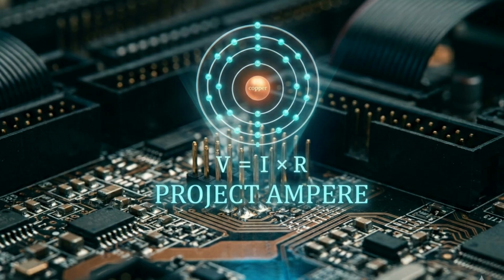When you reach up and flip that ground power switch on the panel, the automated bus logic says, a new power source has been manually commanded. I have checked it. The voltage and frequency are good. I will blindly accept it. And it does the switching automatically. It forcefully opens the APU contactor and instantly closes the ground power contactor. It prevents the human from accidentally crashing the two sources together. It acts as a high-speed, automated traffic cop. It ensures seamless power transfer entirely without relying on human perfection.